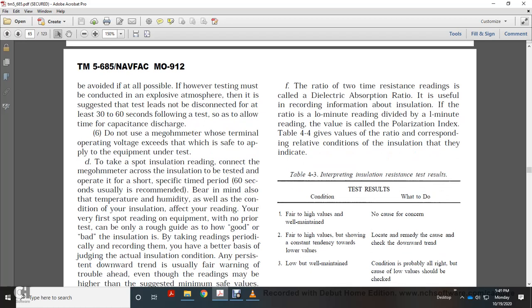Take a spot insulation reading connected with the megohmmeter. Carry out the insulation test for the specified time period of 60 seconds, as usually recommended. Bear in mind that temperature, humidity, and the condition of your insulation affect the reading. Your first spot reading of the equipment, with no prior testing, can only be a rough guide as to how good or bad the insulation is.